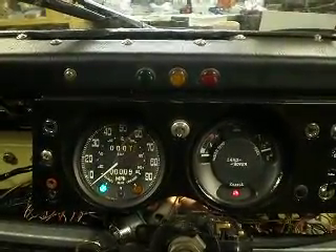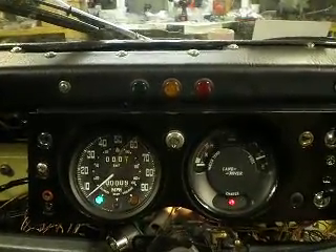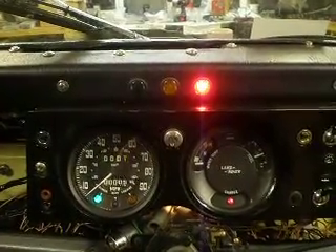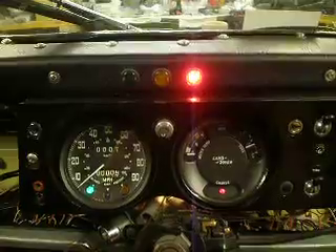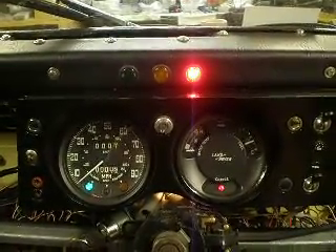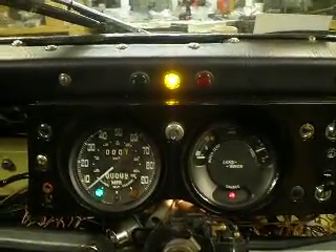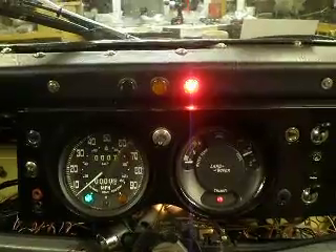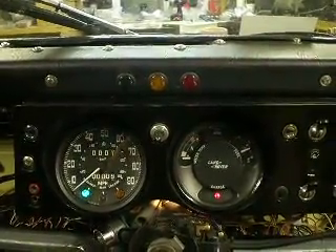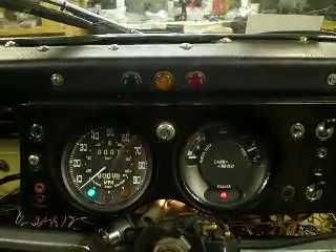In the normal position it will come on and off with the thermostat, so no warning is needed. If you override it to off, you get a bright red danger warning lamp. If you go further to put it into permanently on, you get an amber warning. Turning it off gets you back through fan permanently off and back to safe normal operation.